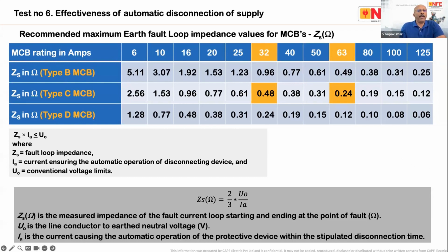So here you can find the type of the MCB and the rating of the MCB. Let's say, for example, you have a 32 amps type C MCB. The maximum allowed fault loop impedance is 0.48 ohm. Also, in the calculations you can see here, 2/3 is the safety factor: 2/3 of the calculated value should be the measured value. So basically, a lot of emphasis is given to this subject, which is automatic disconnection of supply, consisting of an RCD test or an earth fault loop impedance test.